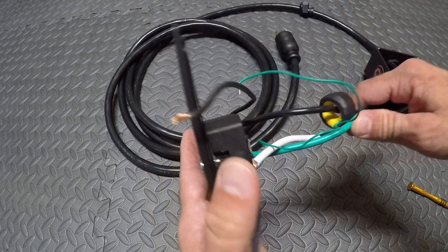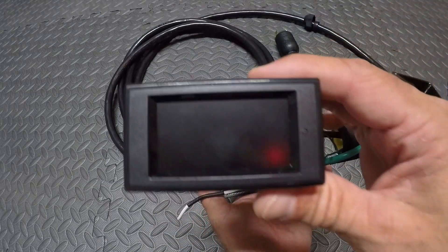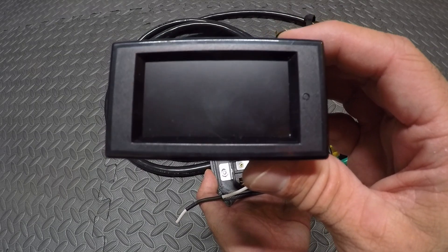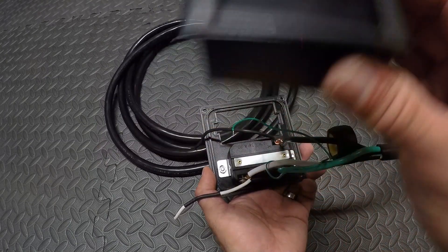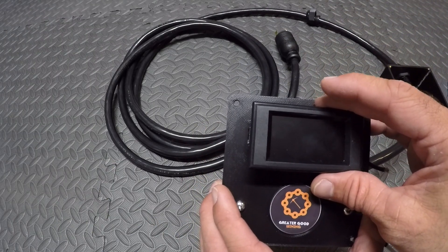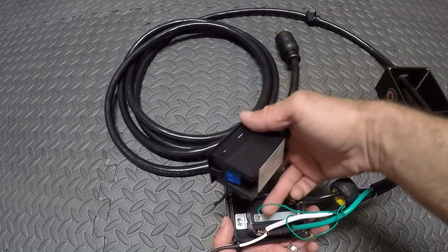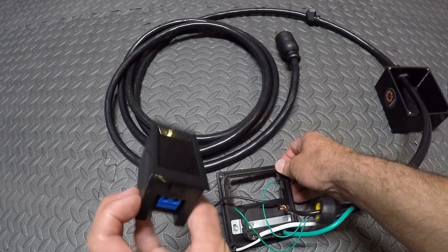So next we're going to wire up the DROK power meter. In my other video I remind people that that little dot on the right means your screen is upright, so if you want to orient this a certain way because you're gonna mount it to the wall, remember the dot on the right means your screen is upright. I don't like popping this in before I wire it up — it's so much easier to wire it without it crammed inside there right up against the plug. You need a little wiggle room to run your wires.